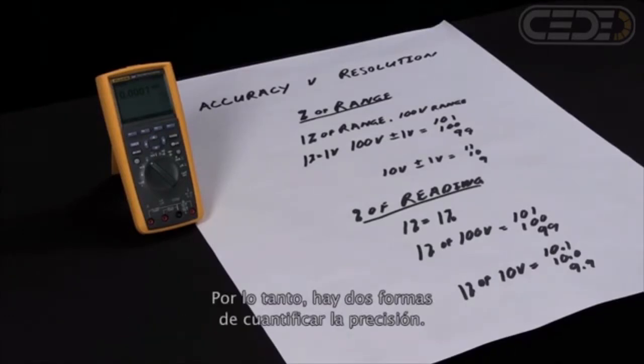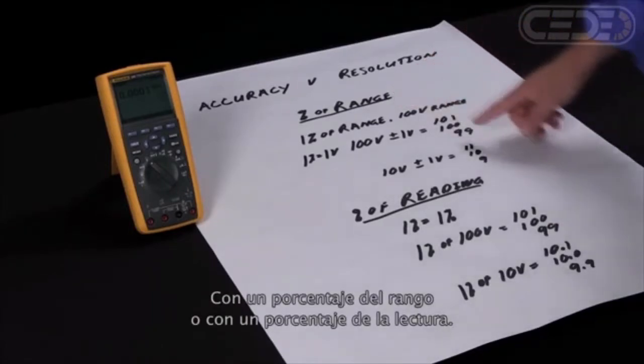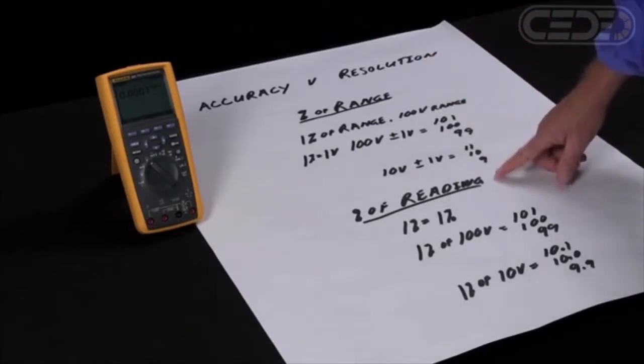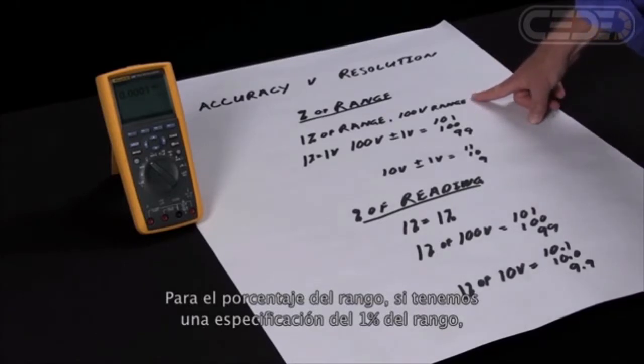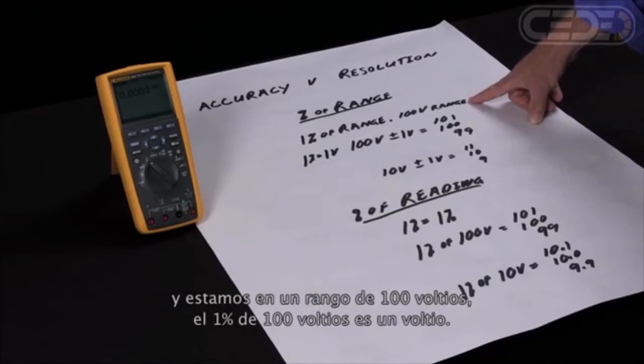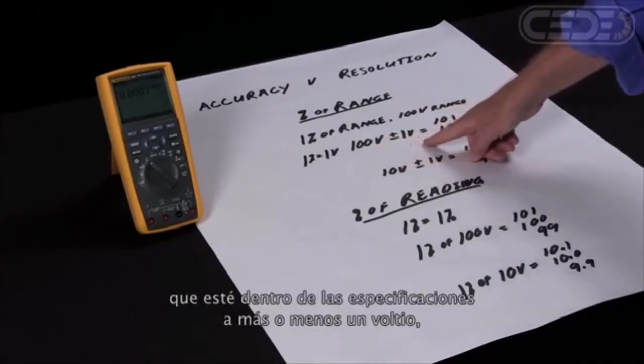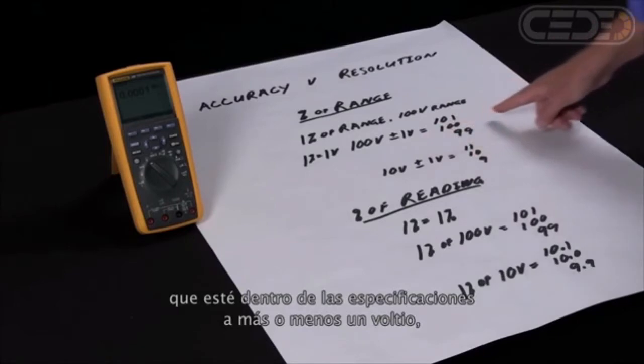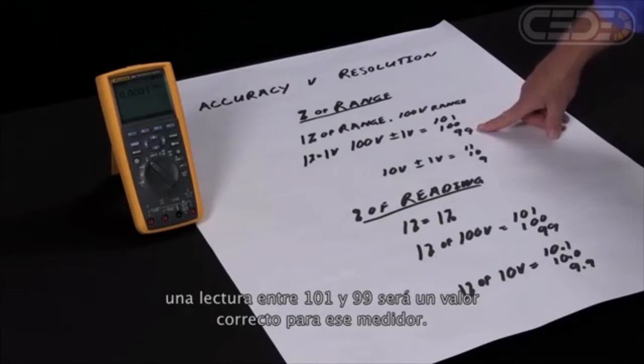There are two ways accuracy is specified: one is percent of range and one is percent of reading. For percent of range, if we have a one percent specification of range and we're on a hundred volt range, one percent of a hundred volts is one volt. So that means with a reading of a hundred volts, that can be within specification at plus or minus one volt — so a reading between ninety-nine and a hundred and one is actually a good reading on this meter.